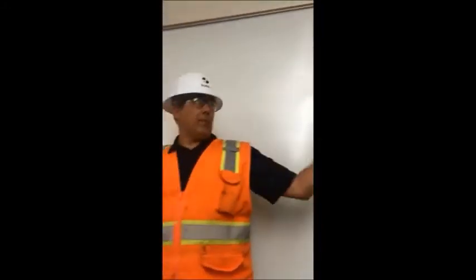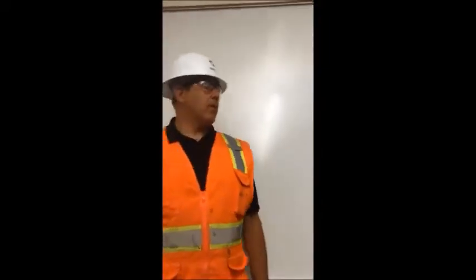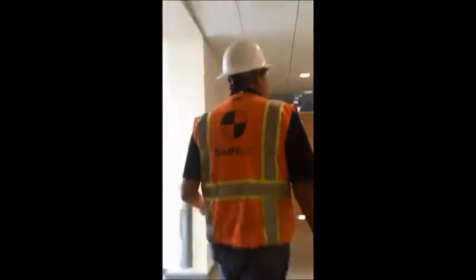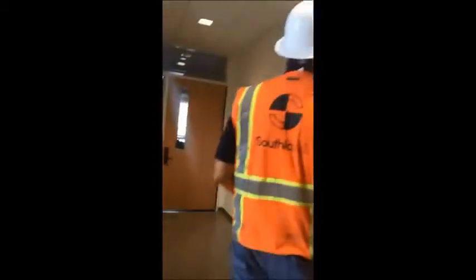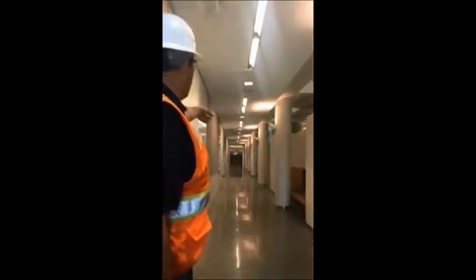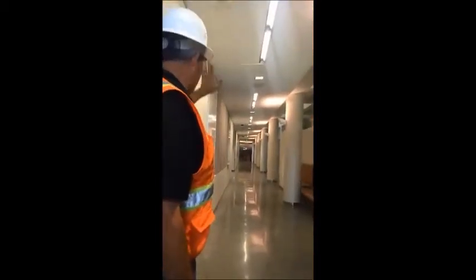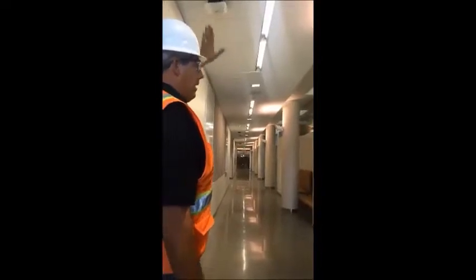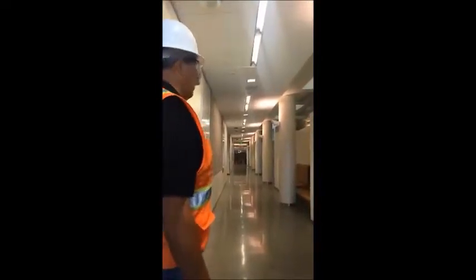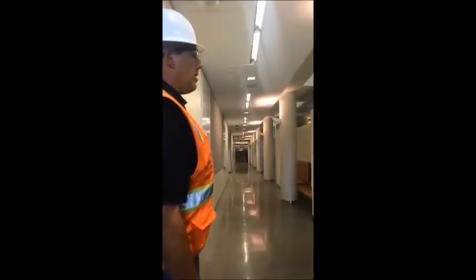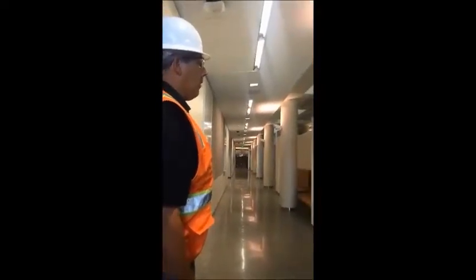Yeah, so you know the main's right through here. The only thing is, as far as the VAVs, the red dots are hot water on VAVs, we'll ask them. Those lines, the hot water VAV lines, go directly down this corridor. And then air handler 3 serves the east side, so the high temp hot water lines go right through here. So it serves air handler 3, the heating hot water coil and the VAV boxes.